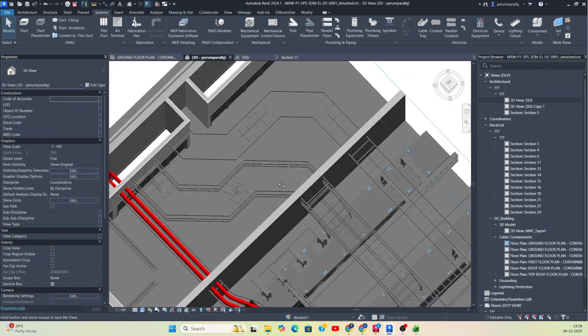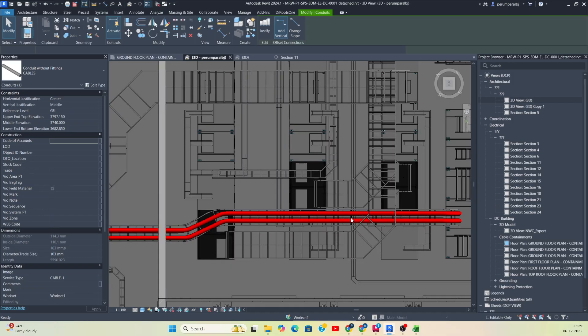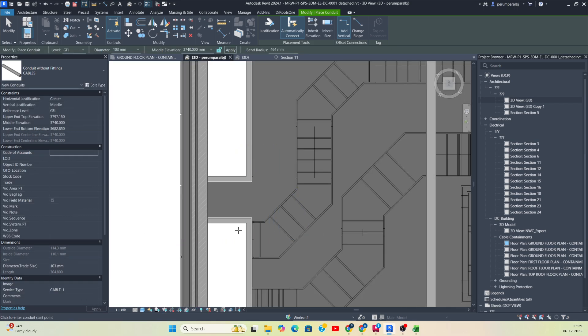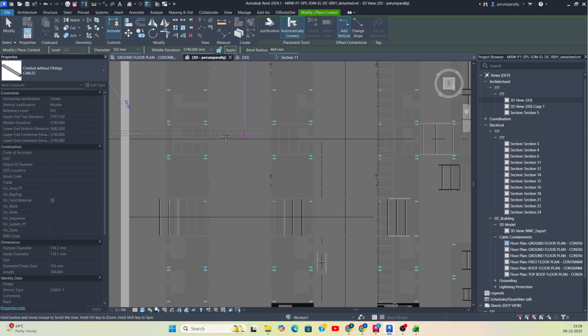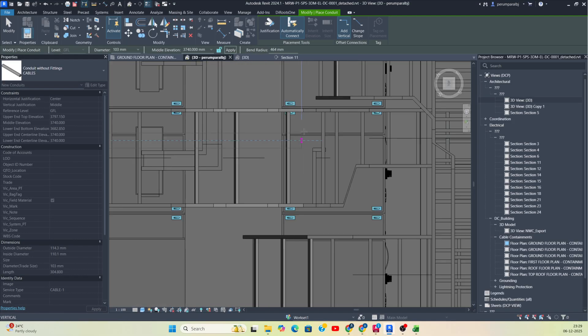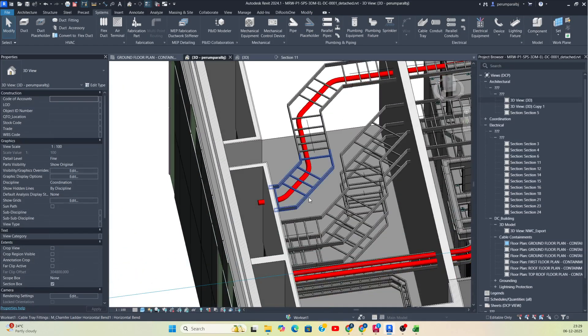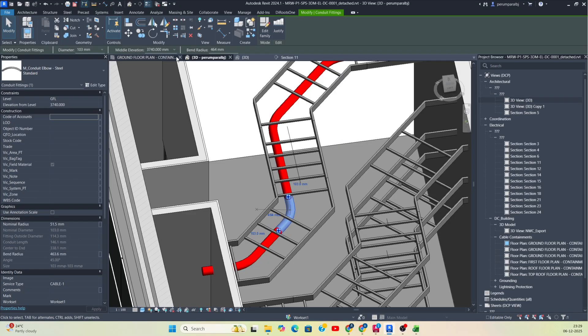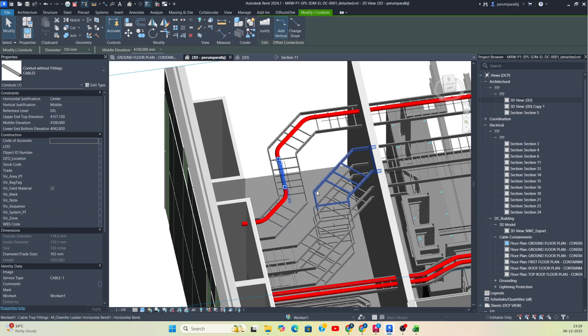If you want to make another conduit through another cable track, you can use the same method even in the 3D view. Just create similar conduits wherever you need. For example, draw from here and run like this — this is the manual method. The cable tray height is 4050, so move this one to height 4100 so it will be above the cable ladder.